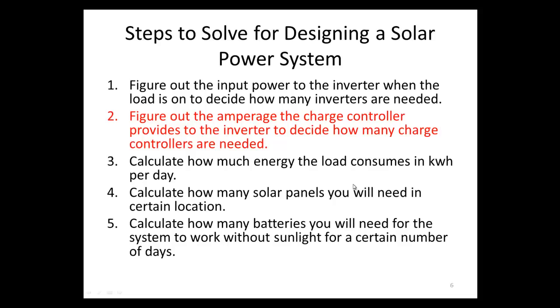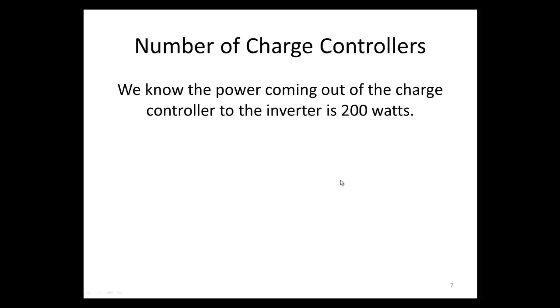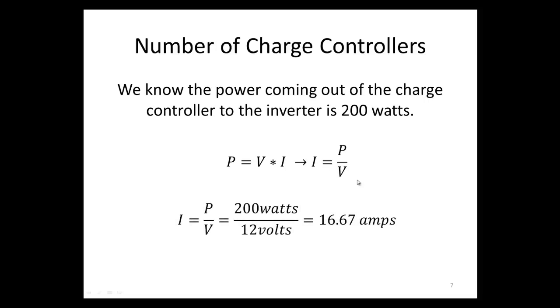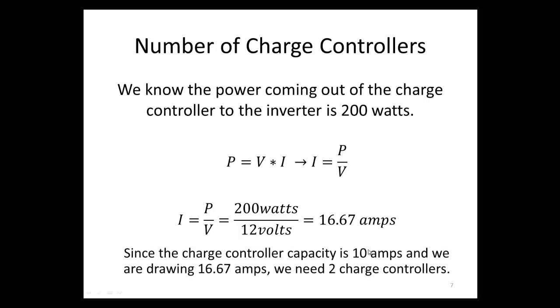Step two: we figure out the amperage the charge controller provides to the inverter to decide how many charge controllers are needed. The power coming out of the charge controller to the inverter is 200 watts. Using the equation P = V × I, we rearrange to get amperage equals power over voltage: 200 watts divided by 12 volts gives us 16.67 amps. Since our charge controller rating is 10 amps and we're drawing 16.67 amps, we need two charge controllers, giving a combined rating of 20 amps.